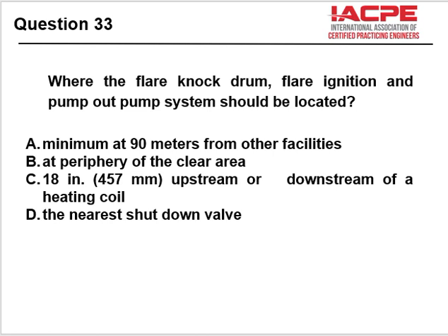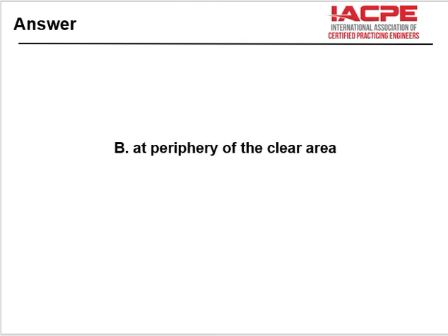Last question, 33. Where should the flare knockout drum, flare ignition, and pump out system be located? Minimum 90 meters at a clear area, 18 upstream or downstream of heating coil, near the nearest shut valve. And it should be at the periphery of a clear area.